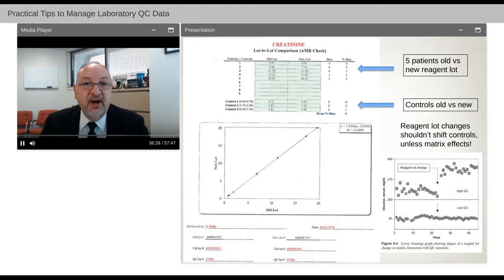of QC. What about a new lot of reagent? We pull some samples, measure them in the old lot and the new lot. So we're looking at patient samples that span the reportable range of that test. And we want to look at QC, old lot versus new lot of reagent. Here you can see five patients, old versus new lot, controls, old versus new. And we can see that everything, reagent lot changes shouldn't shift controls unless there's a matrix effect. Matrix effect would be something like the lower left box where you see a big shift in the high QC, no shift in the low QC when you adopt and implement a new lot of reagent.